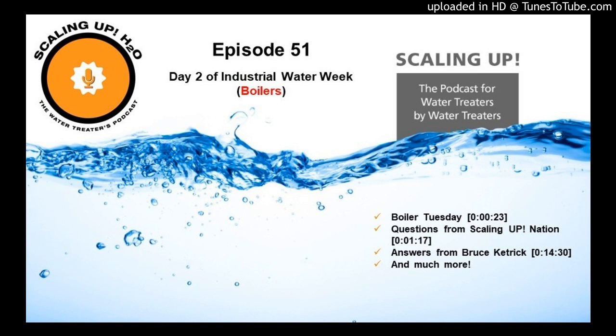Now, most water treaters will simply just put defoamer into the boiler. And folks, that will solve the issue quickly right then and there, but it only solves the surface issue. As soon as that defoamer goes away, you didn't solve anything other than putting something into the boiler. So my suggestion is you take some time and try to figure out exactly what is going on with that boiler.